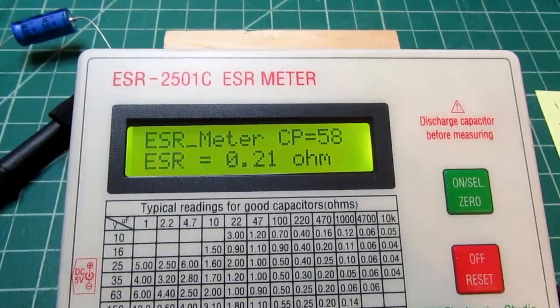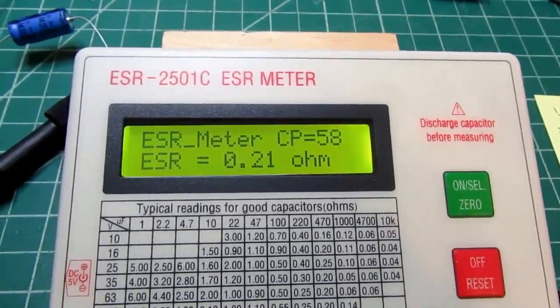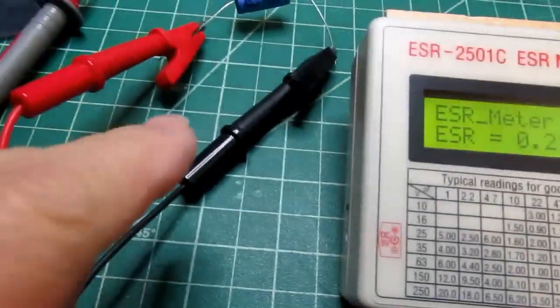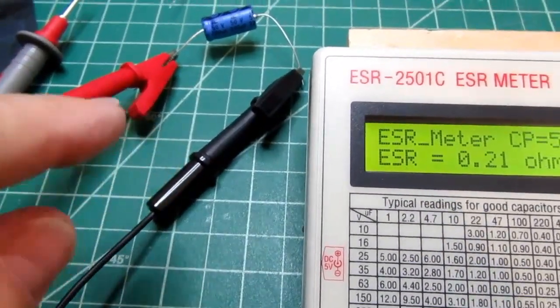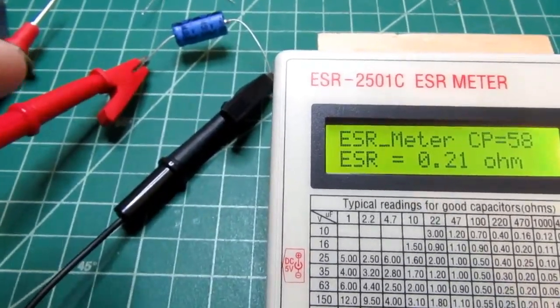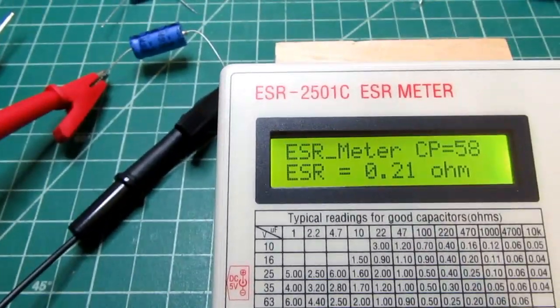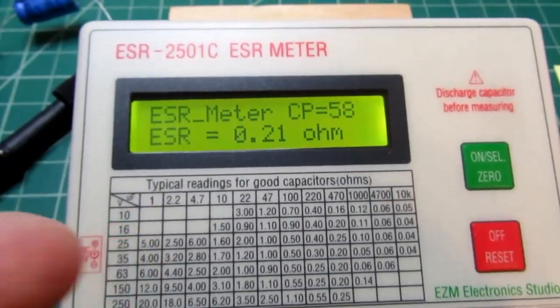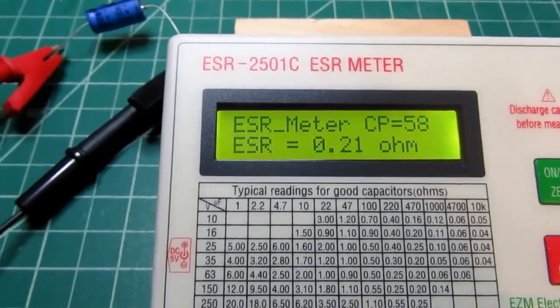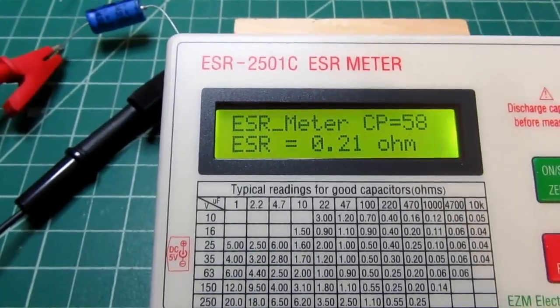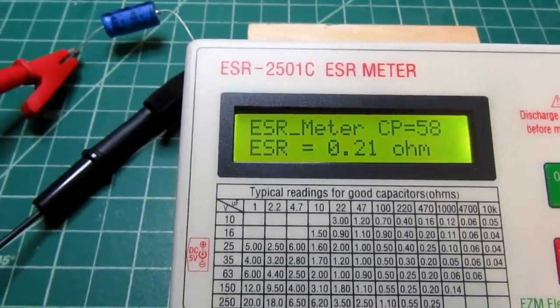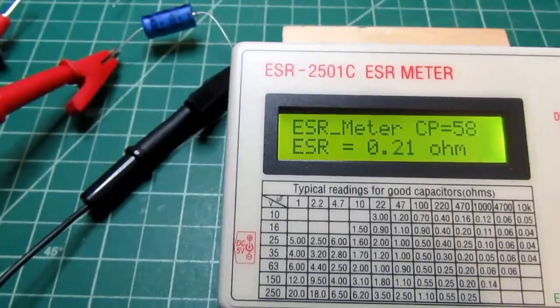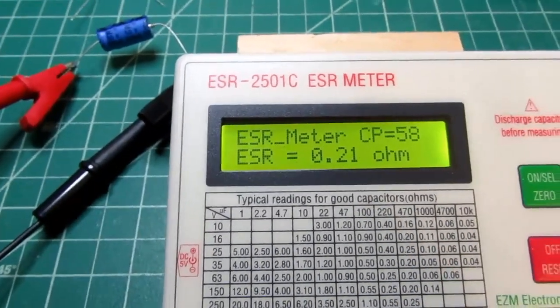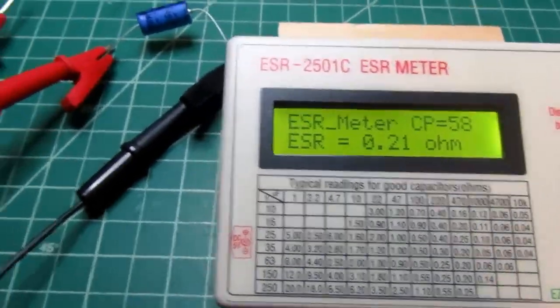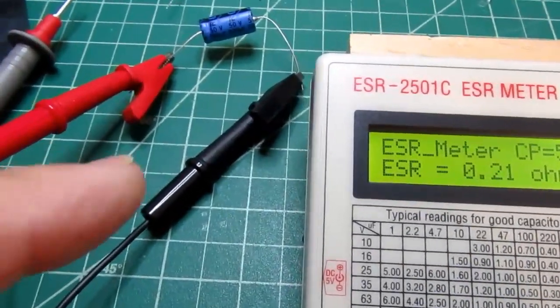It can zero out quite a wide range of resistances. The manufacturer recommends not extending these probes with extension test leads, probably because this may not have the ability to dial it out. But my own empirical test suggests it can dial out a fair amount of resistance as long as it's pure resistance. If you use longer test leads, you'd also have some inductance, which could skew your results. So it's best not to use extensions, but it does seem to be able to dial out pure resistance. Anyway, let's move on.